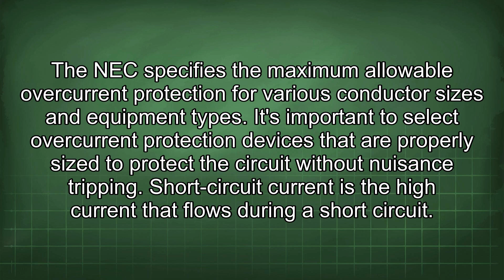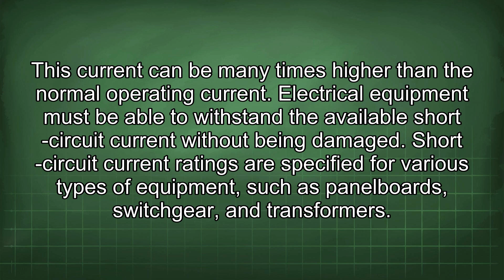Short circuit current is the high current that flows during a short circuit. This current can be many times higher than the normal operating current. Electrical equipment must be able to withstand the available short circuit current without being damaged. Short circuit current ratings are specified for various types of equipment, such as panelboards, switchgear, and transformers. It's important to ensure that the equipment's short circuit current rating is higher than the available short circuit current at its location.